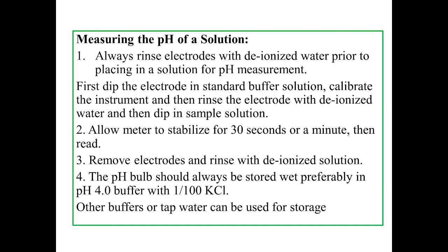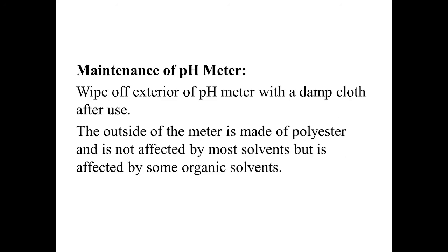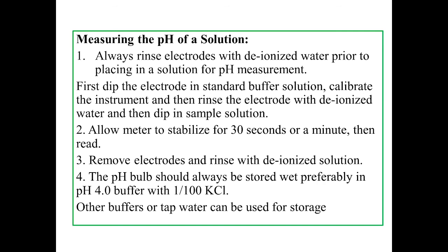The pH bulb should always be stored wet, preferably in the buffer having pH 4 with 1:100 KCl solution. Usually the bulb of the pH probe is covered with a cap wherein a pH 4 buffer is present along with KCl. We can use other buffers also, or we can store it in tap water, but it has to be always kept wet, either by using a buffer plus KCl or any other buffer.